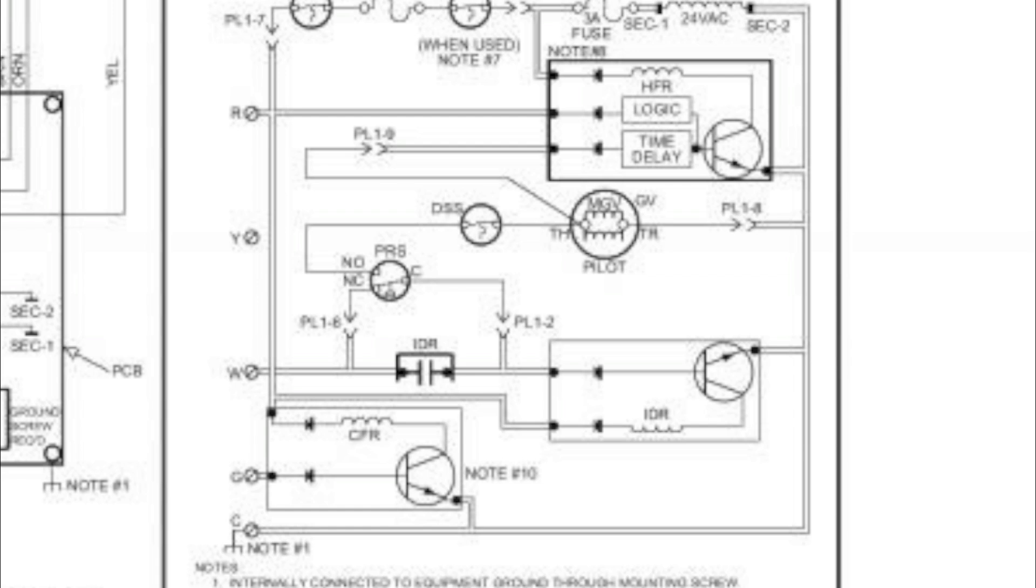So, the pressure switch changes its position. Power passes from, at this point, power passes from W through the closed IDR contacts up through C to normally open, which is now closed, over to a limit switch and the gas valve assembly. That's what says pilot on it there. And that's how that works. You may have to run this over a couple of times to make sure you understand it, but it is fairly simple if you just follow it through.